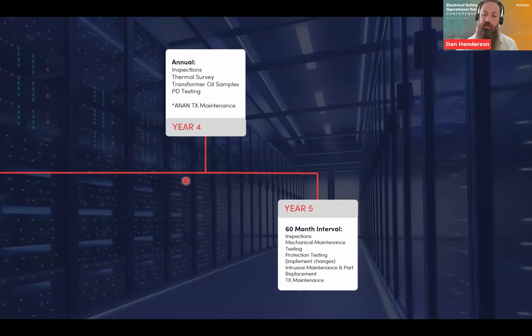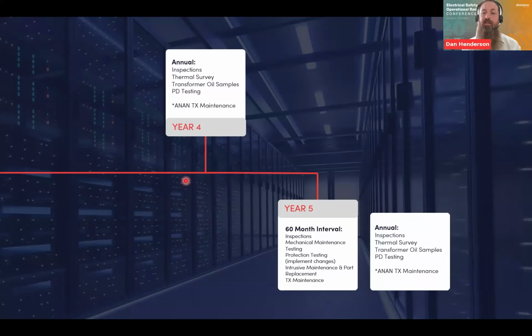Obviously, your transformer maintenance. And what I've added in there is I would still include the annuals. I know a lot of people that do the annuals up until year 4 and then they just plan their maintenance in. I would always do my annuals for 2 reasons. For one, if you can identify any defects, you can bring them into your 5-year shutdown. So you might identify issues with your oil for your transformers, which might need further investigation. You might pick up some low-level partial discharge or a thermal difference on some connections. Then you can focus in on that on the shutdown. But another good thing is it gives you a baseline partial discharge reading and thermal readings close to the event.